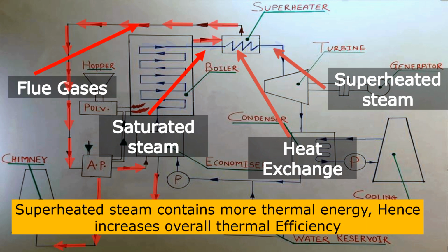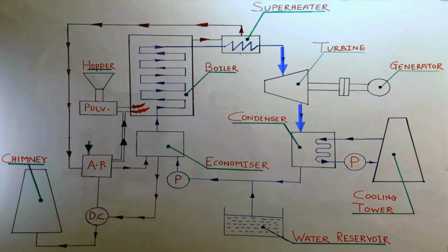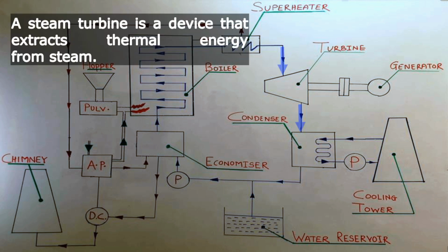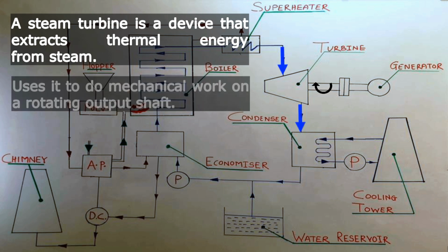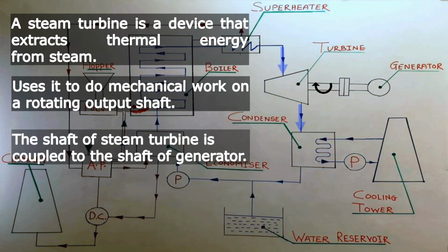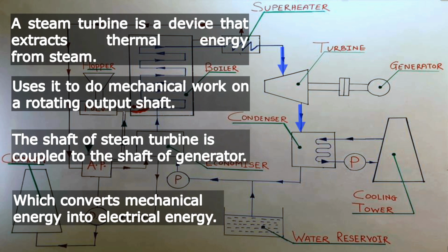Because superheated steam or dry steam contains more thermal energy, hence it increases the overall efficiency of the thermal power plant. Now this superheated high pressure steam is passed over the turbine blades. Turbine blades are mounted on the turbine shaft. Hence it rotates the turbine shaft, and finally it produces mechanical work. Now you can see here the turbine shaft is mechanically coupled with the generator shaft. Hence the mechanical work is converted into electrical energy with the help of generator.